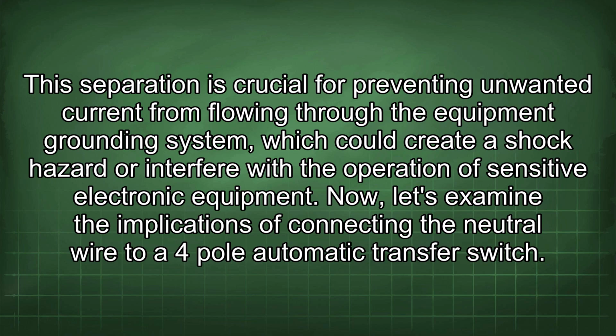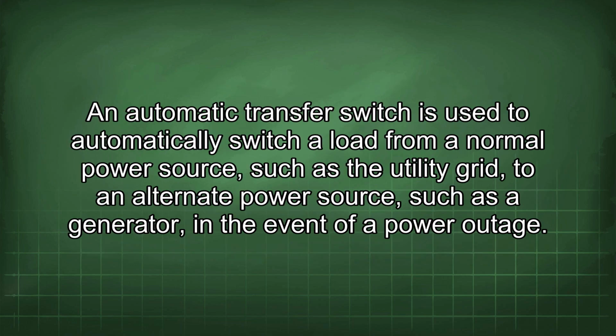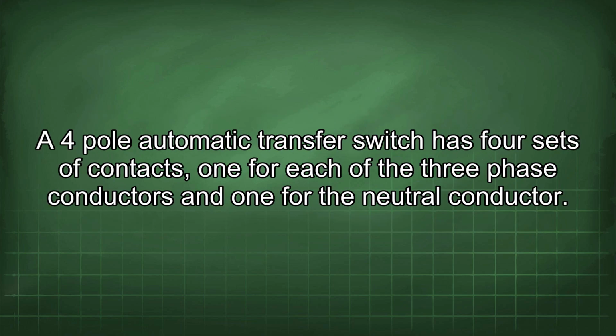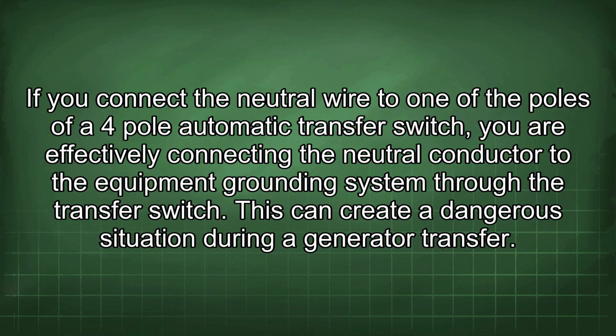Now let's examine the implications of connecting the neutral wire to a 4-pole automatic transfer switch. An automatic transfer switch is used to automatically switch a load from a normal power source, such as the utility grid, to an alternate power source, such as a generator, in the event of a power outage. A 4-pole automatic transfer switch has 4 sets of contacts, one for each of the 3-phase conductors and one for the neutral conductor. If you connect the neutral wire to one of the poles of a 4-pole automatic transfer switch, you are effectively connecting the neutral conductor to the equipment grounding system through the transfer switch.